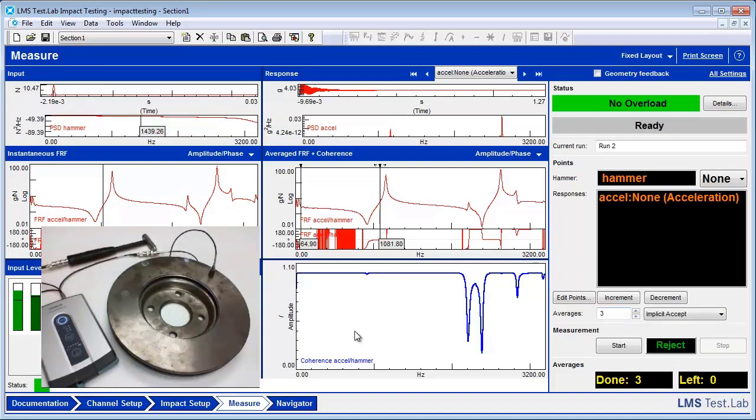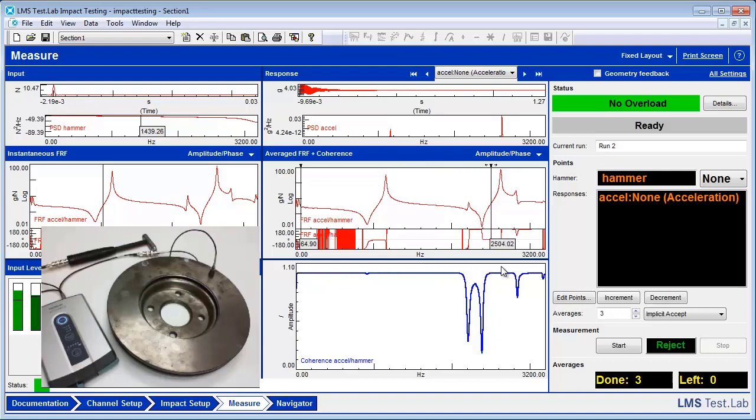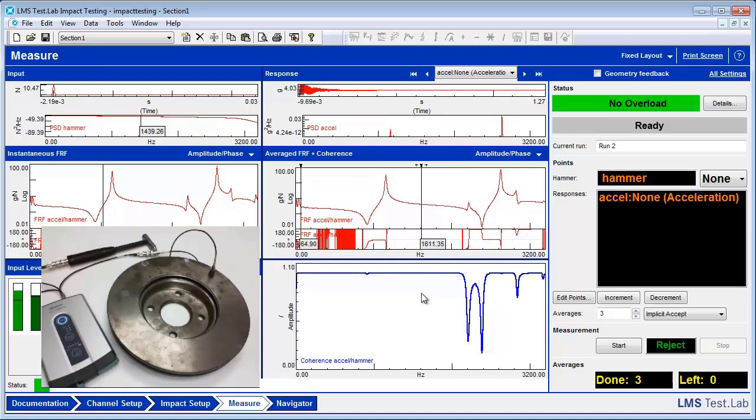One thing we want to check is our coherence, which we see in this bottom right window here. Coherence tells us how repeatable our measurement is from hit to hit. When the coherence is equal to one, that means it's repeatable. We do see a couple of dips here in our coherence. But these do line up with dips in the FRF also, which we call anti-resonances. And this is expected and is normal.